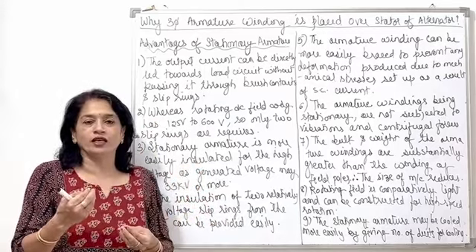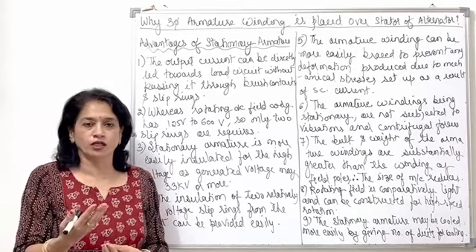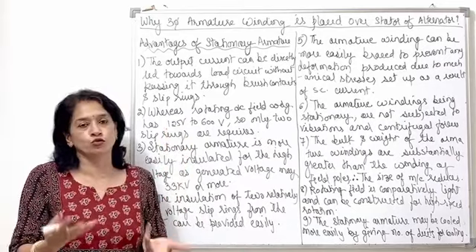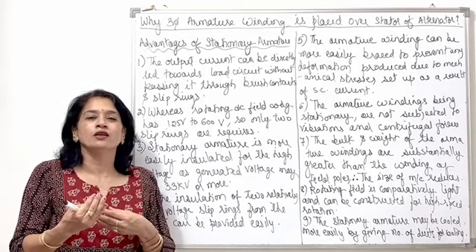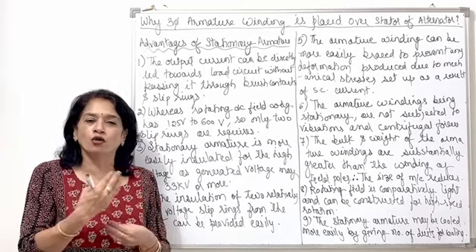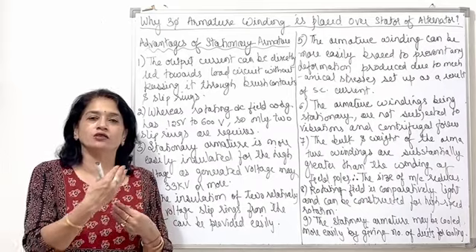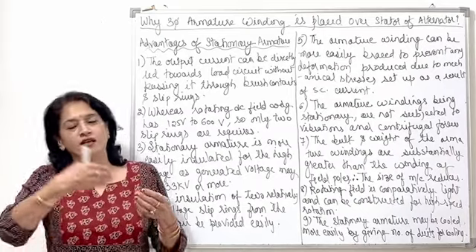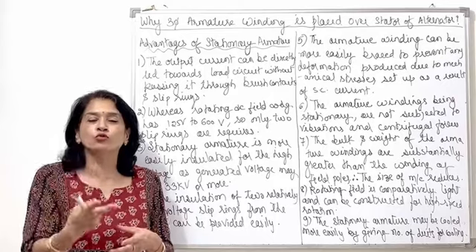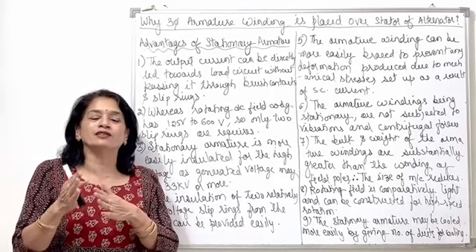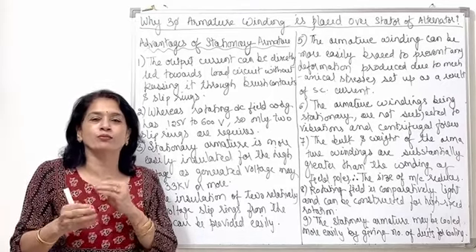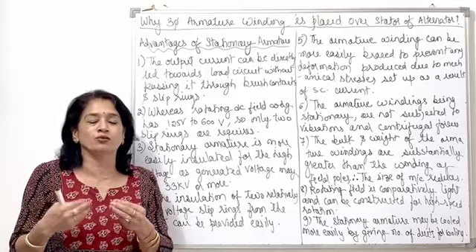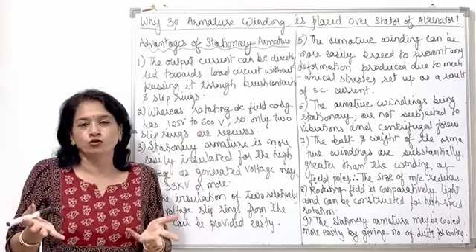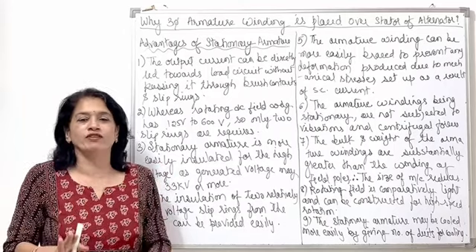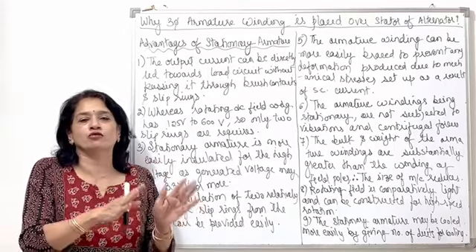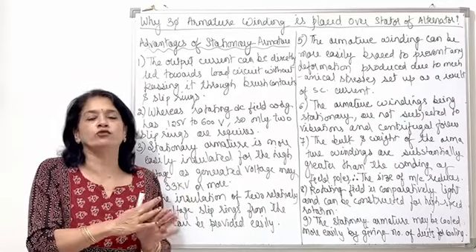Whereas the rotating DC field winding, which is given over the rotor, handles only 125 volts to 600 volts. So it is quite easy to handle such a small voltage carrying circuit over a rotating rotor, connected with the DC excitation through only two slip rings. And those slip rings are not so costly, because those slip rings along with the brush arrangement have to handle small voltages.